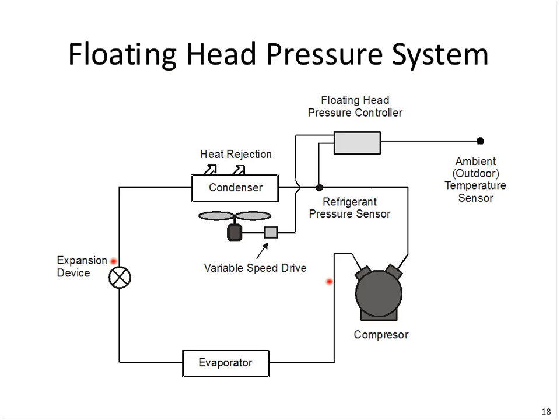Also, I guess our picture's depicting a reciprocating compressor here. With a screw compressor, the velocity needed on the discharge here to separate the oil from the refrigerant is a function of an oil separator design. And lower first cost oil separators generally do not provide the capacity to do adequate oil separation at lower pressures. So we end up with a carryover of oil, and that may be an inhibiting aspect of attaining floating head pressure.